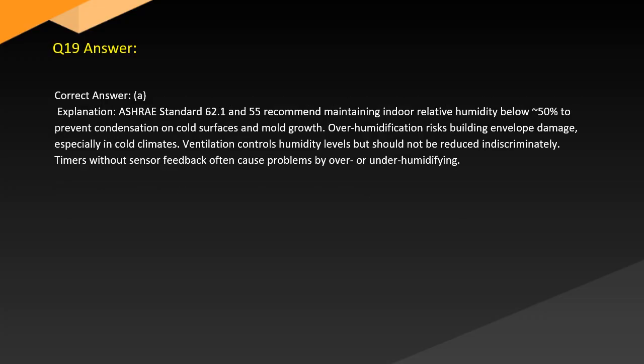Answer. Correct answer, A. Explanation. ASHRAE Standard 62.1 and 55 recommend maintaining indoor relative humidity below 50% to prevent condensation on cold surfaces and mold growth. Overhumidification risks building envelope damage, especially in cold climates. Ventilation controls humidity levels but should not be reduced indiscriminately. Timers without sensor feedback often cause problems by over or underhumidifying.